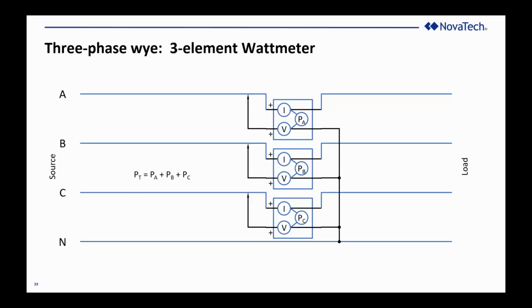So in a three-element wattmeter, you're passing the current through the current element on each of the three phases, and the three voltages are exact analogies to the single-phase wattmeter, where you're looking at the voltage of each phase relative to a common ground. That ground, that could be neutral.